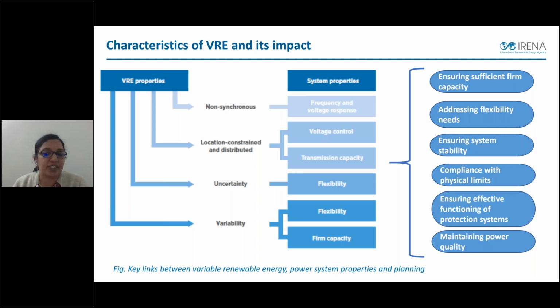Before planning to integrate high shares of renewables, and especially VRE, system operators and stakeholders must understand the characteristics of VRE and its impact on system operation. I think the speakers before me have explained quite a few of them, but I would just like to highlight the main challenge-creating characteristics of VRE. They are non-synchronous in nature because they are interfaced with the grid through power electronic devices. So they decouple from the frequency and voltage of the system, and therefore the system behaves differently compared to a system with high shares of conventional generation, especially under network events. They are also location constrained, because renewable resources are not available everywhere. So they have to be placed at locations where the resources are highly available, and this might require significant network extensions or otherwise lead to network congestion.